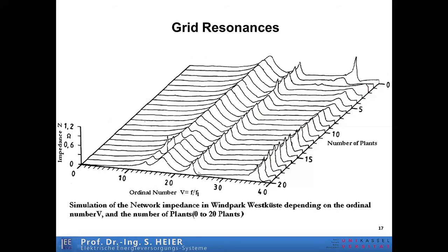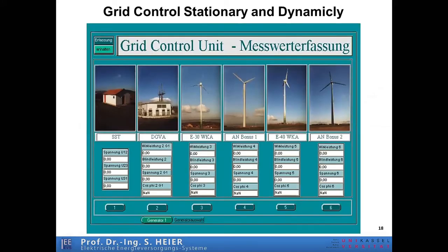On the other side, you have impedance near zero, and this means when you have a voltage and impedance nearly zero, then you get a very high current. It means we have a current resonance point. Yeah, and so sometimes it can be especially critical when you have large distances and a very strongly calculated grid.